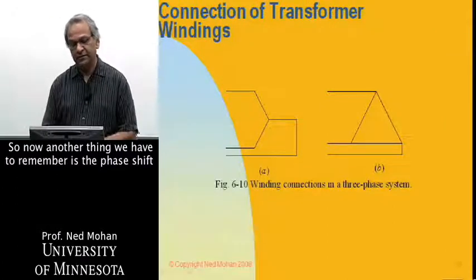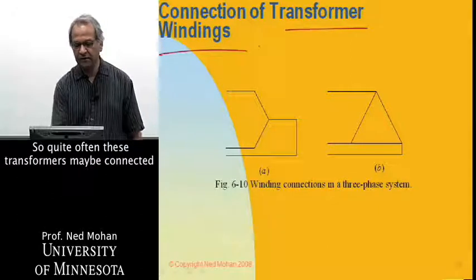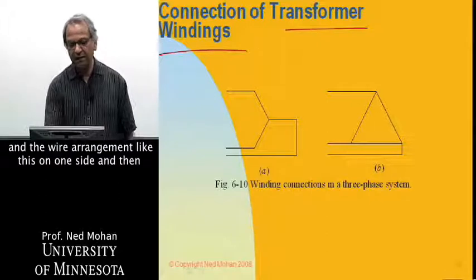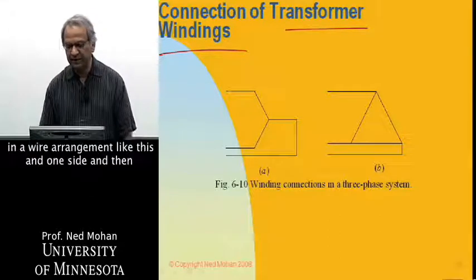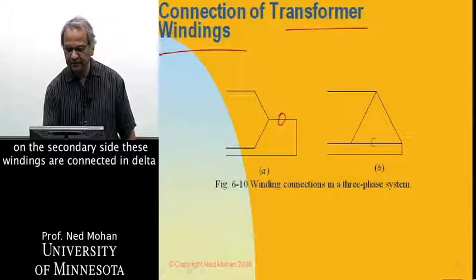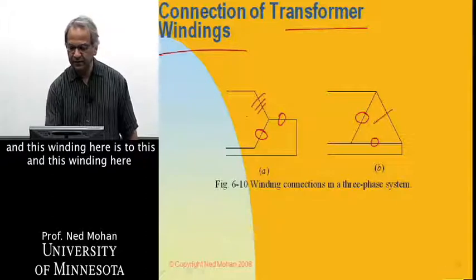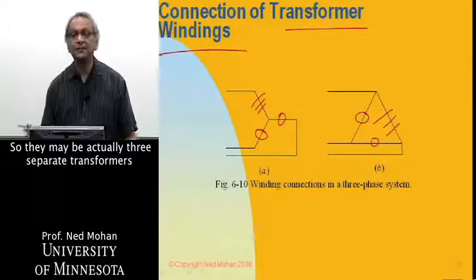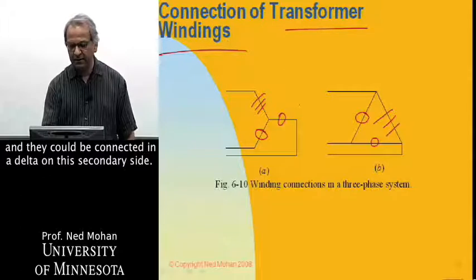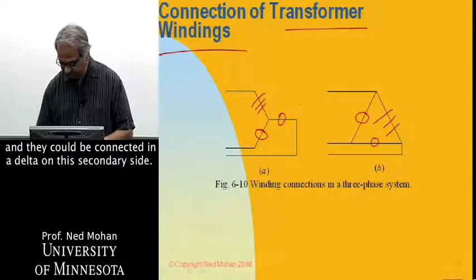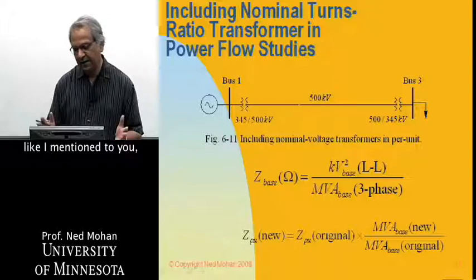The other thing we have to remember is the phase shift that takes place because of transformer winding. So quite often, these transformers may be connected in a Y arrangement like this on one side, and then on the secondary side, these windings are connected in delta. So this winding is coupled to this winding, and this winding here is to this, and this winding here to this over here, like this. So they may be actually three separate transformers which are connected in a Y on this side, and they could be connected in a delta on the secondary side. So we'll see the phase shift there.